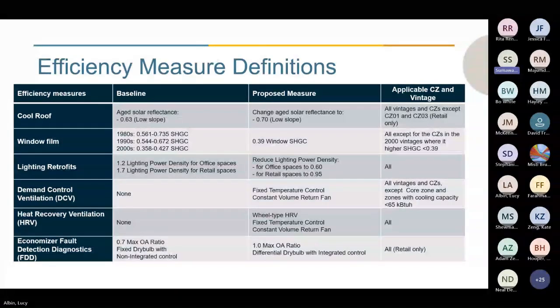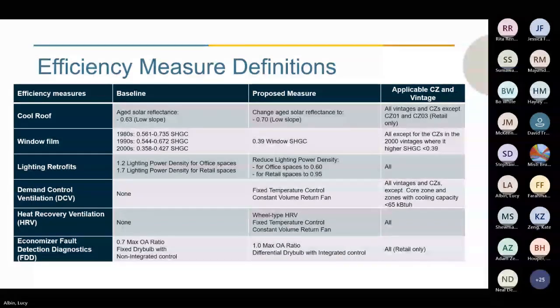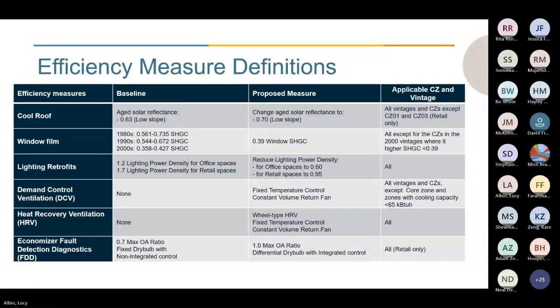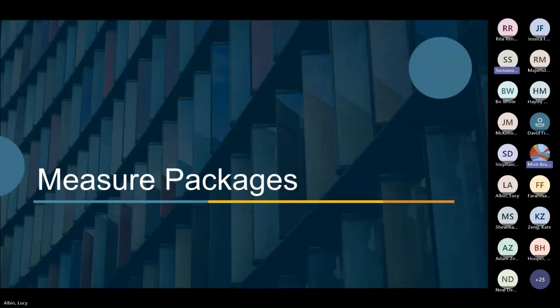So we simulate a faulty economizer with these specifications right here. And for proposed, we fixed this issue, adjusted the max outdoor air to 1, and changed the economizer to differential dry bulb and integrated control. So these measures only apply to medium retail prototypes because small office cooling capacity is way below the required capacity to include the economizer in most of the zones. Next slide.